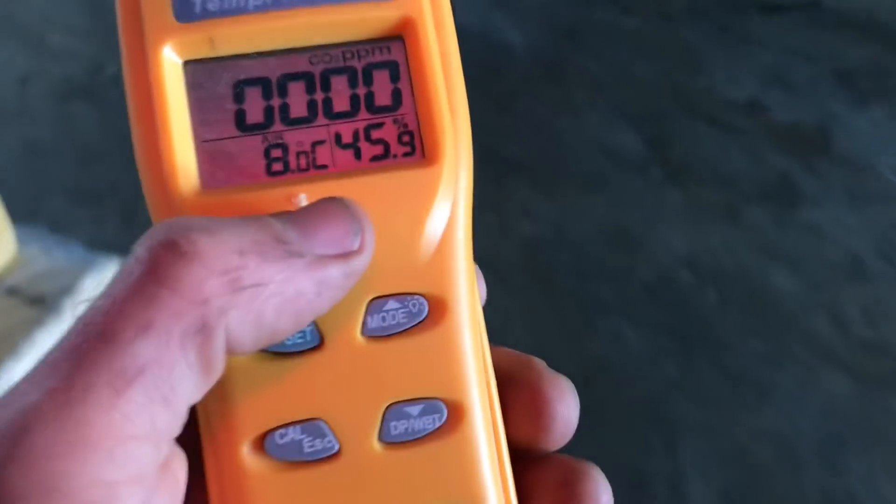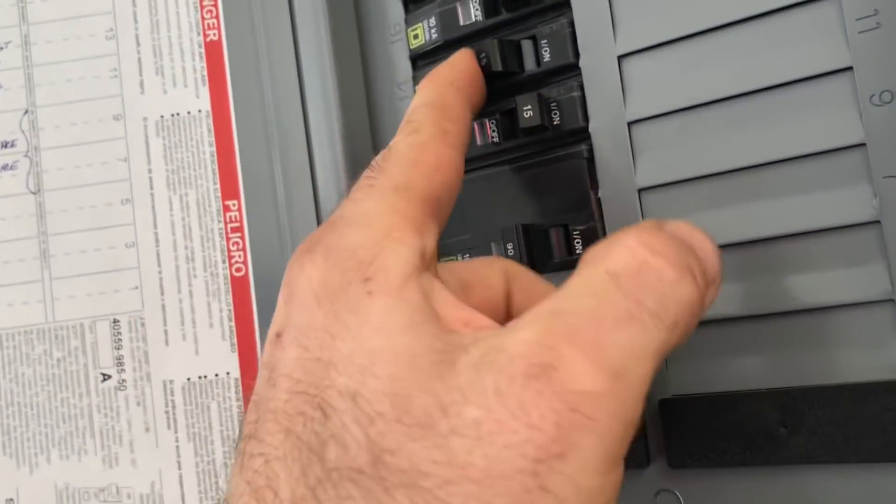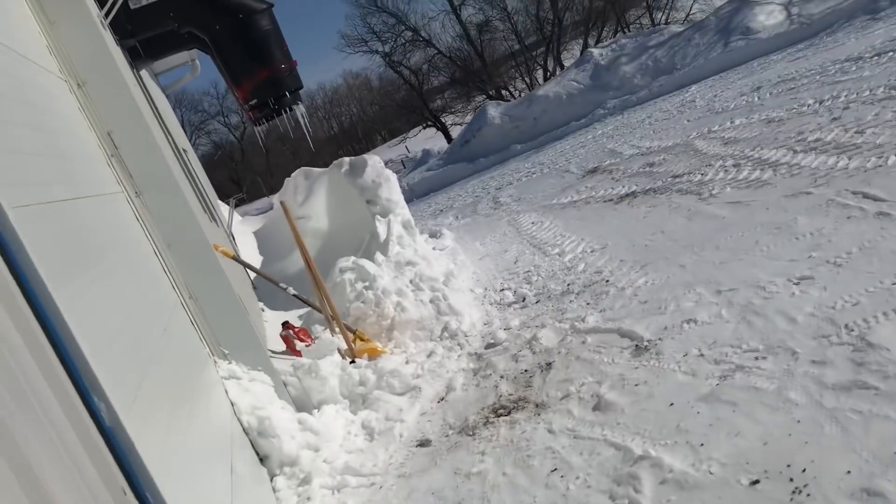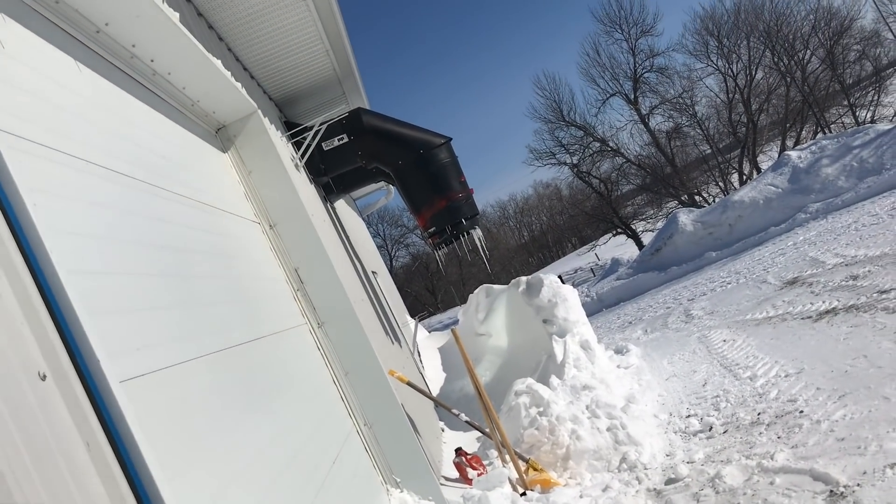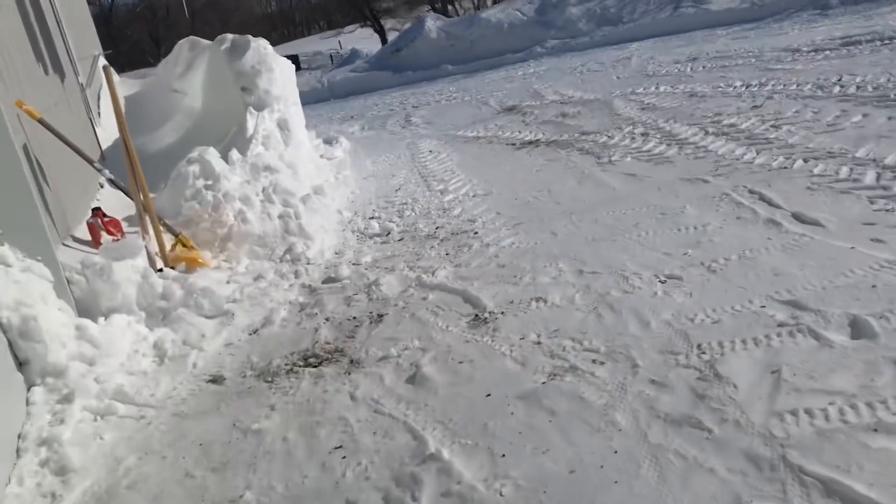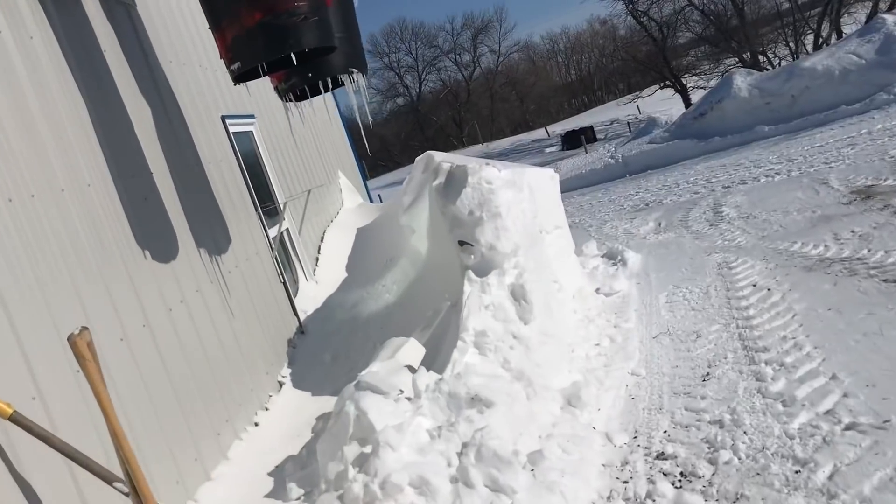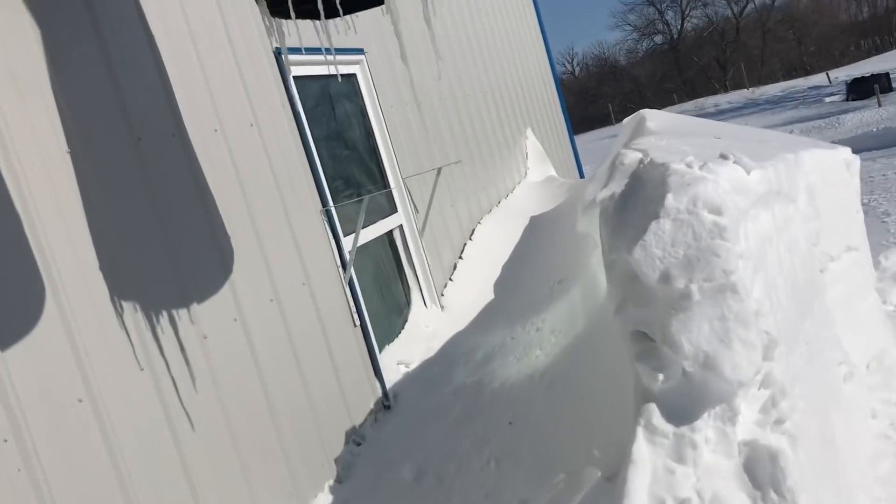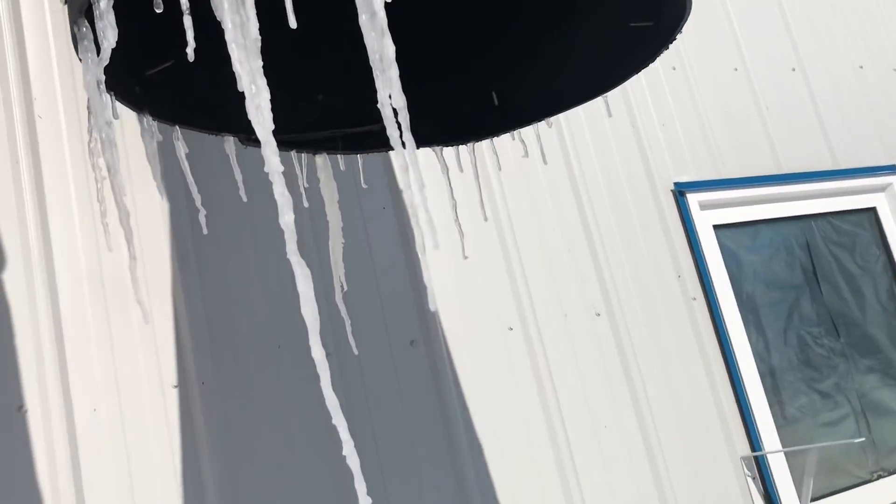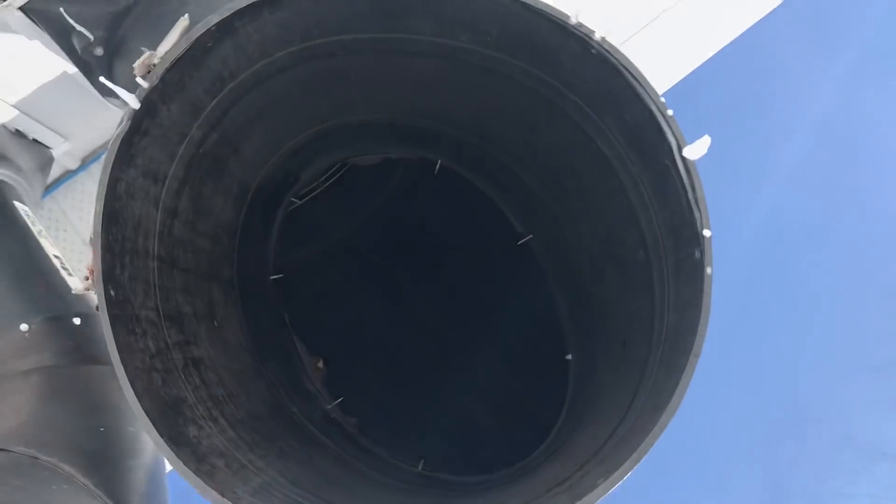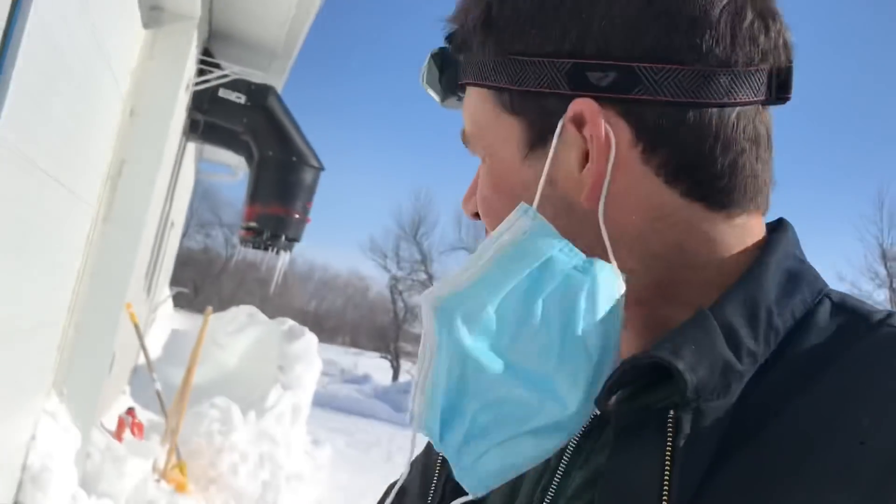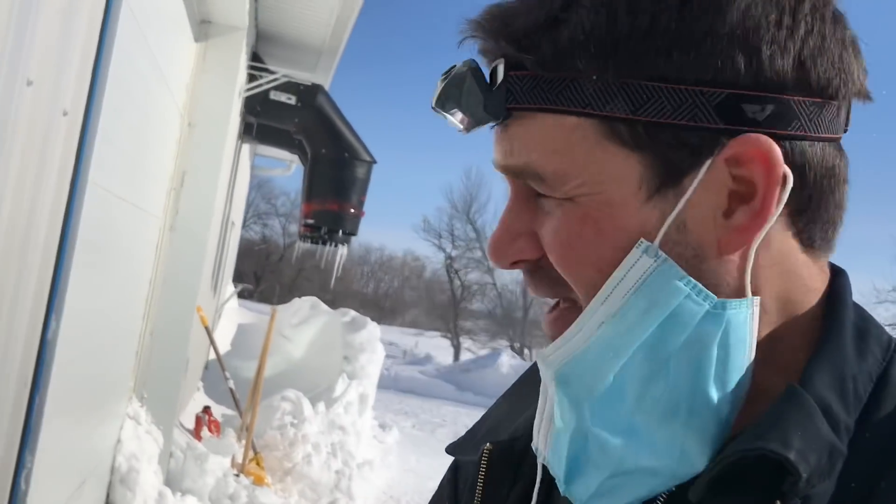I hear you. Okay. So my next thing I'm going to do is turn the fan on. Oh, it's so bright. Both fans are on. She is purging the air out now. Well, that air feels heavy. Sounds like I have a bearing going on the one motor there. I'll have to add a little bit of oil to it. So I'm going to go load that semi-full of corn and I'll come back and I'll see what the CO2 levels are reading when I get back.